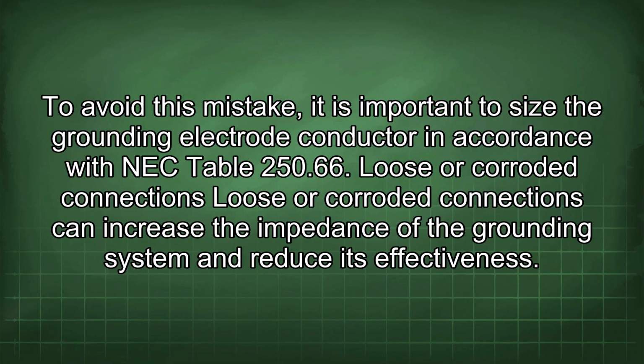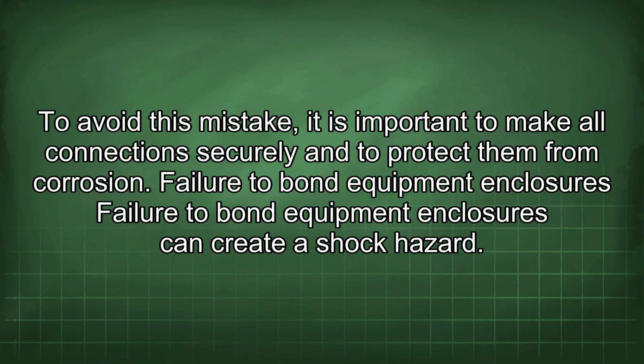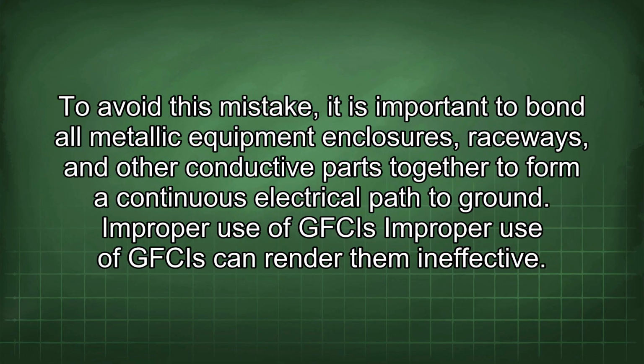Loose or corroded connections can increase the impedance of the grounding system and reduce its effectiveness. To avoid this mistake, it is important to make all connections securely and to protect them from corrosion. Failure to bond equipment enclosures. Failure to bond equipment enclosures can create a shock hazard. To avoid this mistake, it is important to bond all metallic equipment enclosures, raceways, and other conductive parts together to form a continuous electrical path to ground.